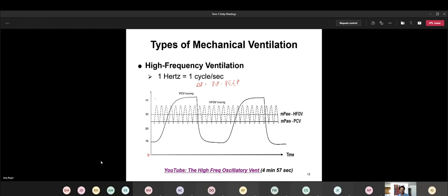It could be maybe 45, in which case delta P would be 35. But again, it'll work either way. If you estimated this to be about 45 PIP, delta P would be 35. But I was just trying to make it easy for my eyes and just say, I see 40 right here. So let's just say it's pretty close to 40.